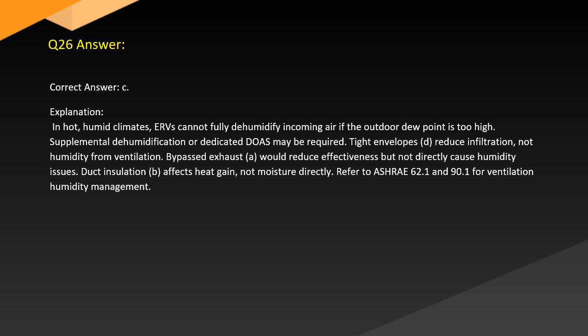Answer. Correct answer: C. See explanation. In hot, humid climates, ERVs cannot fully dehumidify incoming air if the outdoor dew point is too high. Supplemental dehumidification or dedicated DOAS may be required. Tight envelopes reduce infiltration, not humidity from ventilation. Bypassed exhaust would reduce effectiveness but not directly cause humidity issues. Duct insulation affects heat gain, not moisture directly. Refer to ASHRAE 62.1 and 90.1 for ventilation humidity management.